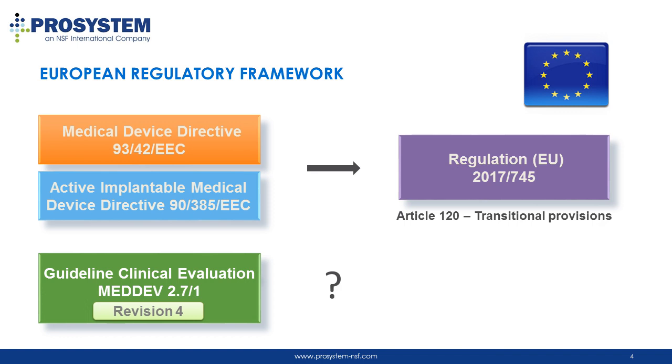Therefore, a new revision of this guideline and/or additional guidelines of the European Commission is needed for further guidance on clinical evaluation. The requirements on clinical evaluation from the regulation are consistent with the recommendations from the MEDDEV guideline. We could even say that this guideline can be considered complementary to the regulation, in the sense that it offers practical guidance on how to fulfill some of its requirements. So you might consider to still adopt the MEDDEV guideline in your own internal process as an orientation to prepare clinical evaluations.